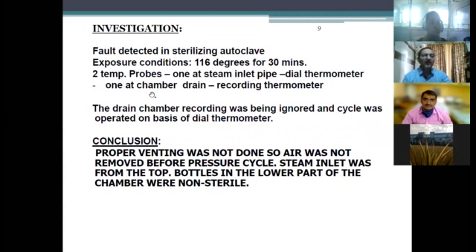Okay, going ahead. So the investigation was done, and a fault was detected in the autoclave. You understand? See over here. There were two temperature probes in an autoclave. We are using steam for sterilization, so these bottles of dextrose were being sterilized by autoclaving. The exposure conditions were 116 degrees for 30 minutes, and two temperature probes were there: one at the steam inlet, a dial thermometer, and one at the chamber drain, which was a recording thermometer. The problem which was seen was that the drain chamber recording was being ignored, and the cycle was operated on the basis of only the dial thermometer.